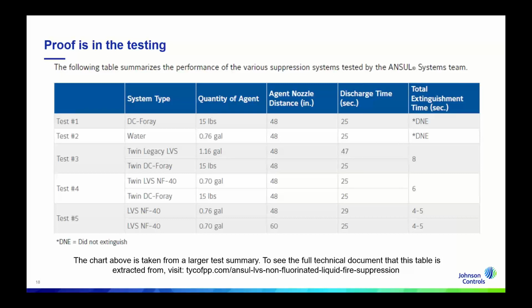Some of the other agents were not effective at achieving extinguishment in these specific test scenarios. That's not to say they're not sufficient or adequate fire suppression methods, but in this comparison they weren't able to achieve the same successful results that we achieved with just NF40. It's important to note that this testing was done with high pressure hydraulic fluid, which lowers the auto ignition temperature, requiring the agent to be best in class for cooling of those superheated surfaces and ensuring reignition doesn't occur.